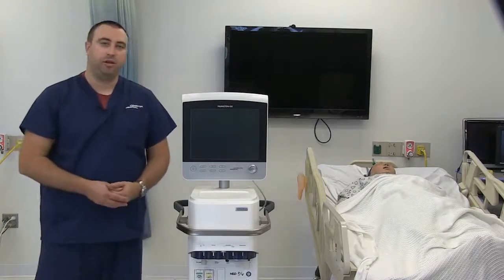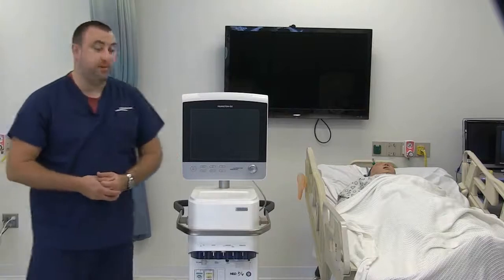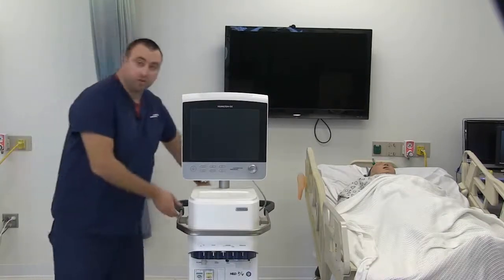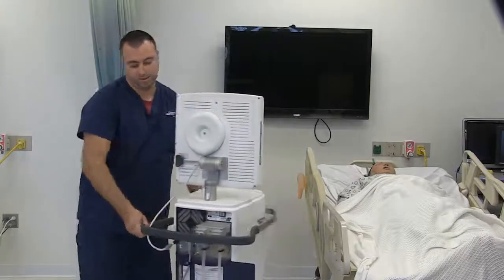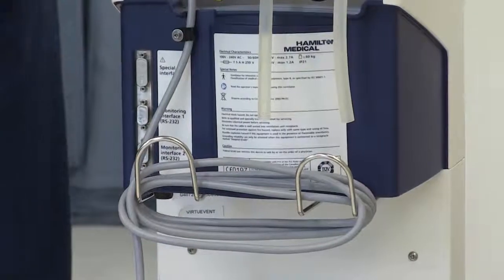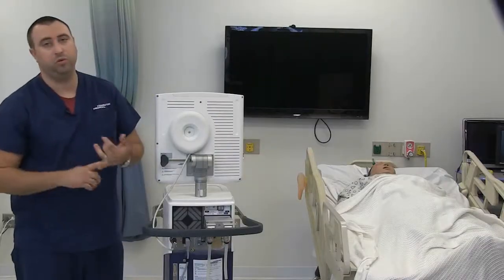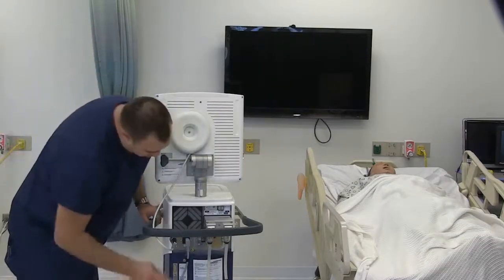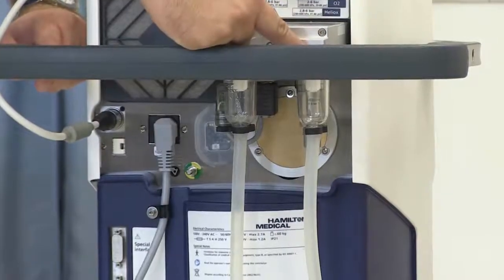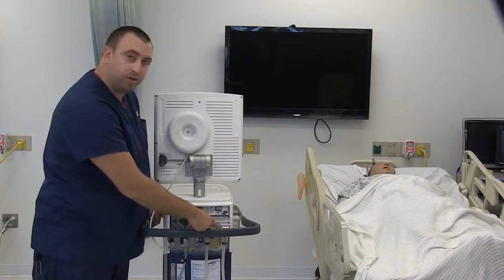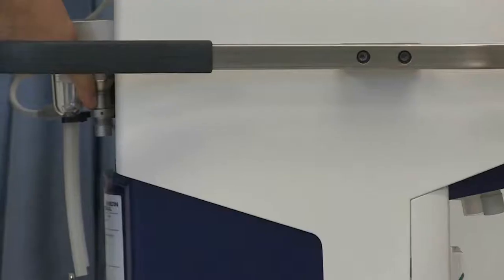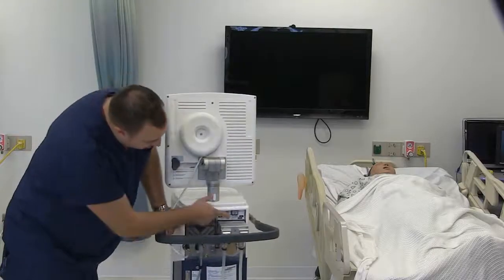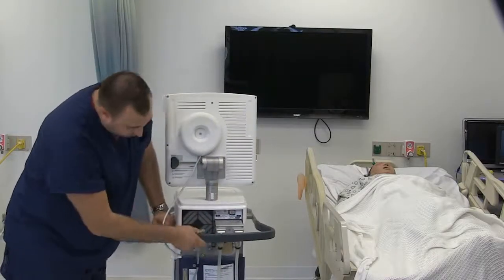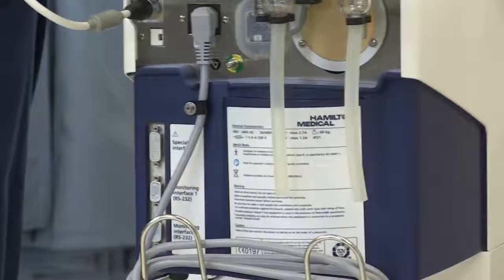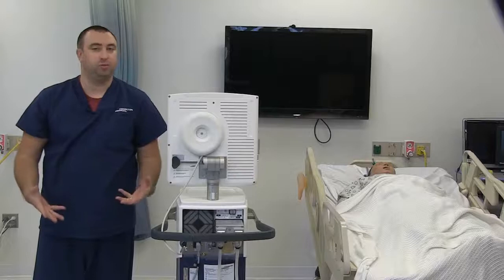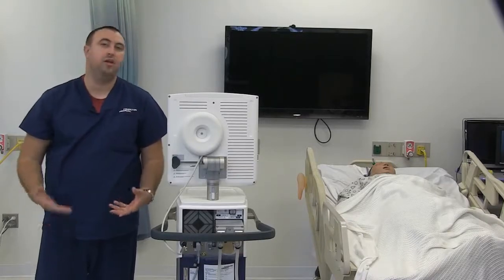And today I'll be talking about usage and demonstration of the Hamilton G5. I'm going to start in the back of the vent. So starting down here, we have our RS-232 ports, which are good for hooking up to nurse monitor and nurse call buttons. Up here, we have our air inlet, high pressure O2 inlet. Over here we have our high pressure heliox inlet, on off button. And then down here we have our gas reservoir. So if the patient has an inspiratory flow demand that is greater than what's in the circuit, they can pull off of that.